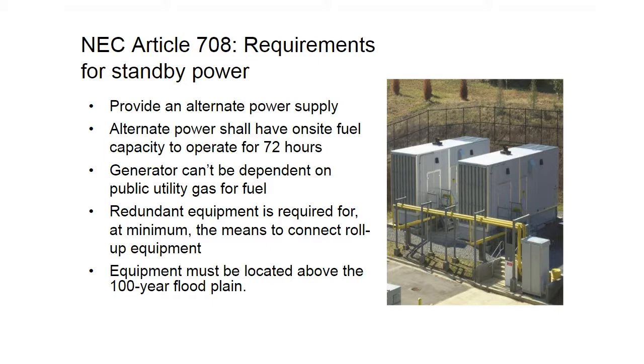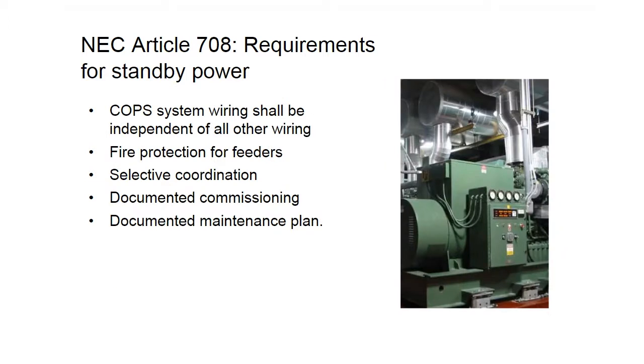All the equipment must be located above the 100-year floodplain. With COPS, any system wiring has to be independent of utility wire. So if you run wire common with the generator, common with other utility, you have to make sure it's separate. Any feeders have to be fire protected. It must be selectively coordinated. You do need to have a documented commissioning plan showing that it was commissioned and tested, and then they want to make sure you have a documented maintenance plan that you're going to maintain the system once it's in operation.